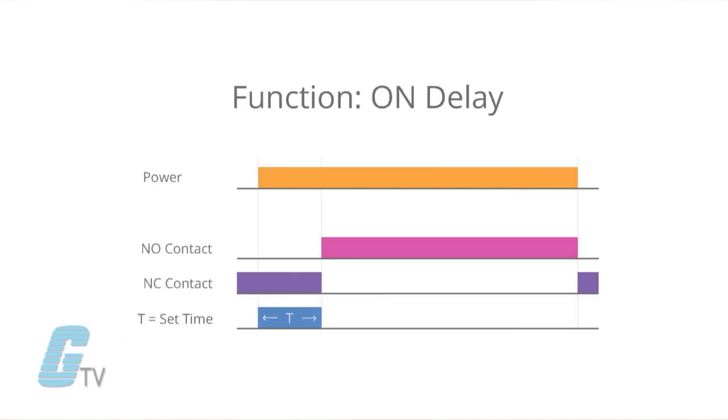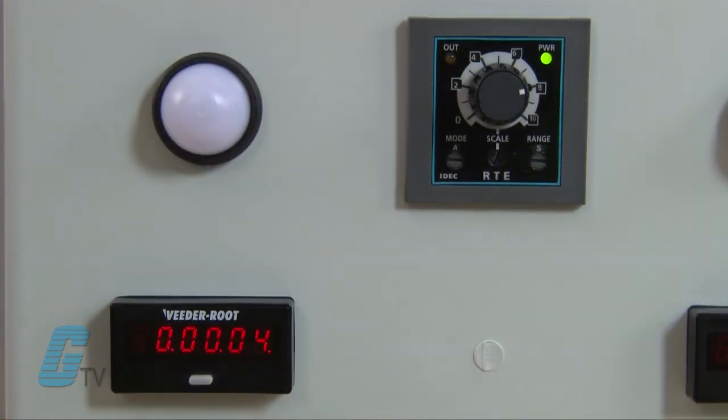Taking a look at an on delay timer, the timing function begins when power is applied. The contact will not change state until after the time elapses. It will then change state and turn on until it is removed from the power source.